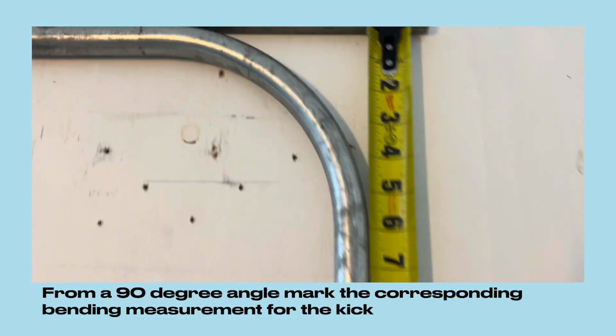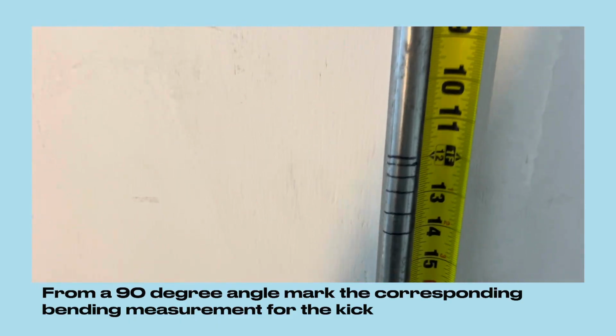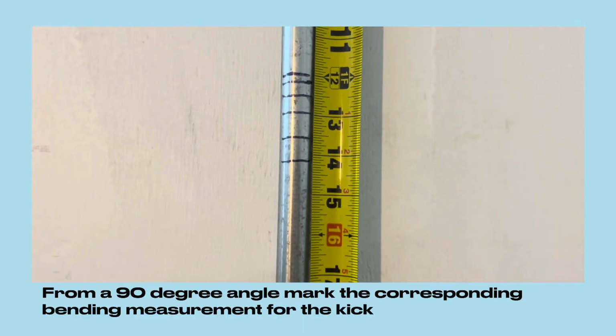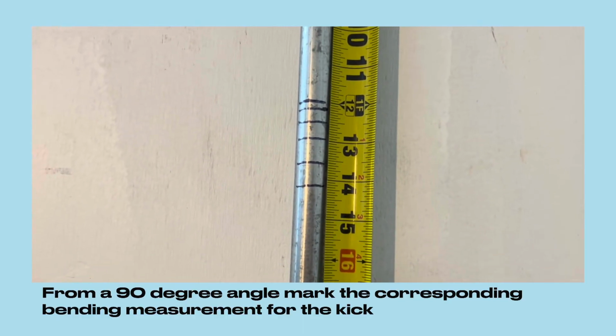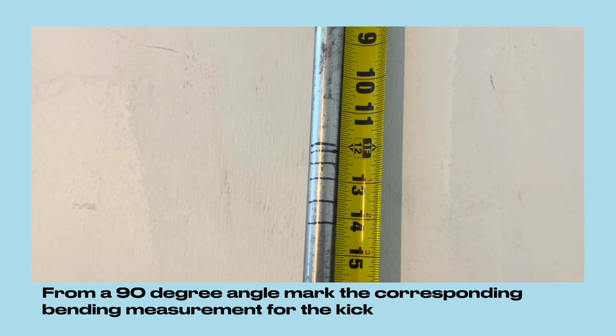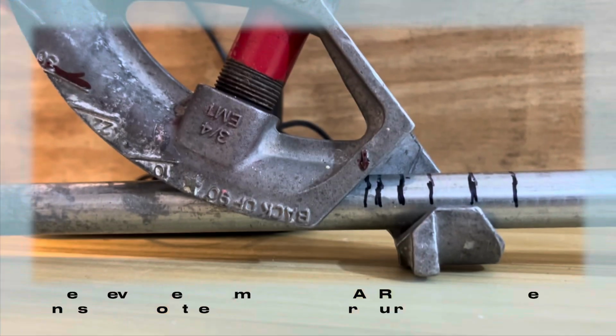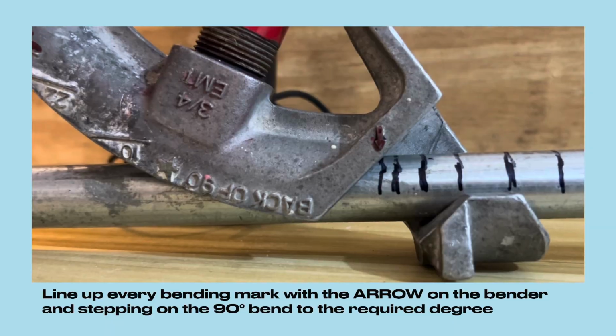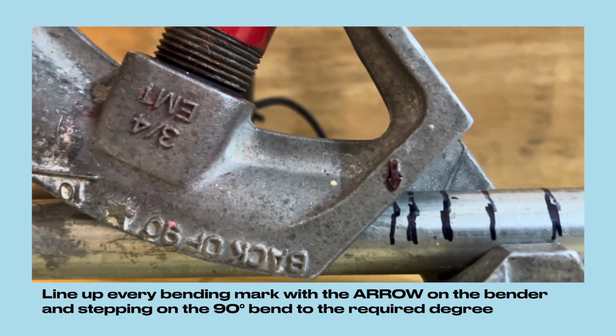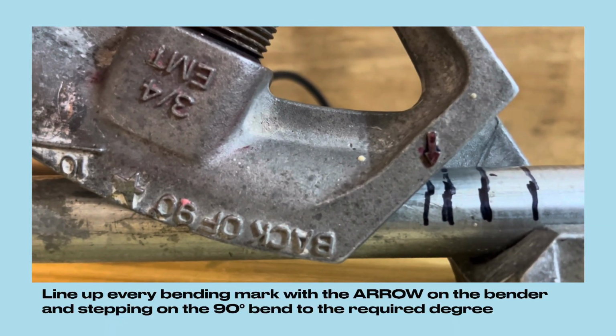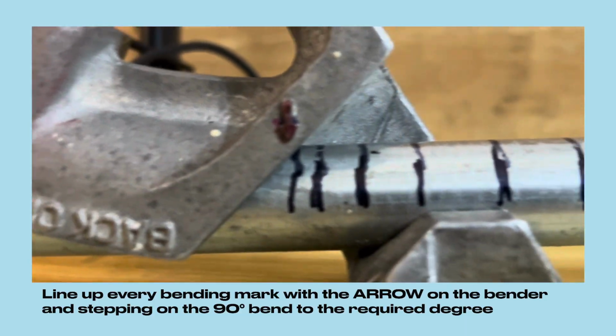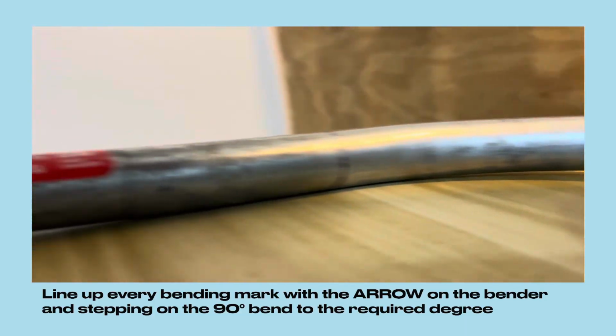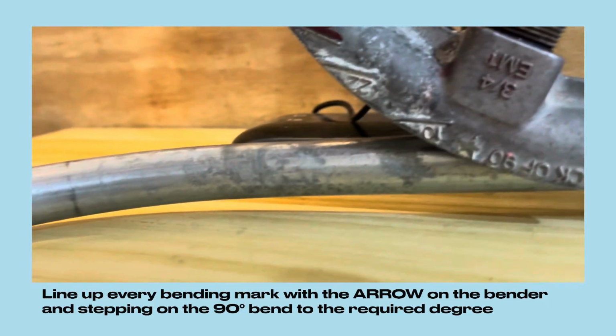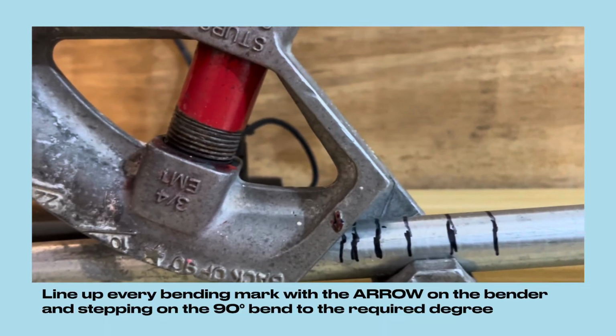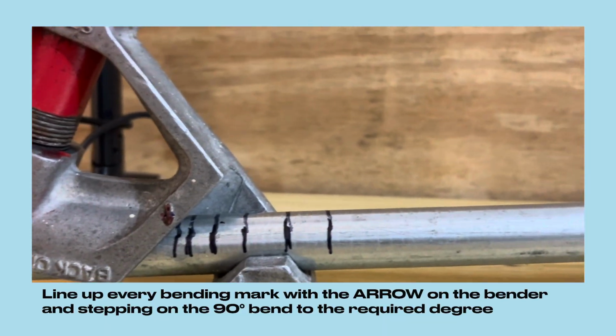So I'm going to show where to place the bending marks in the bender. Finally, to bend the conduit, you will place the bending mark lining up with the arrow in the bender, and the 90 in that position, and you will bend the required degree.